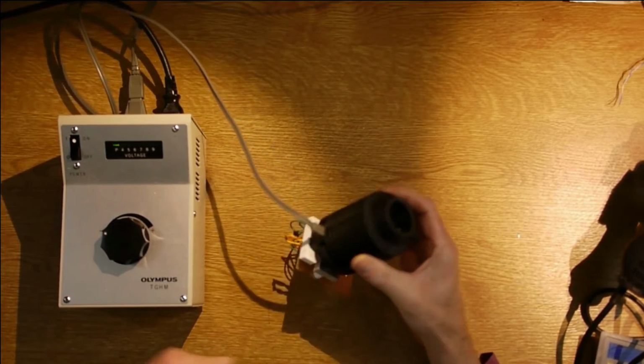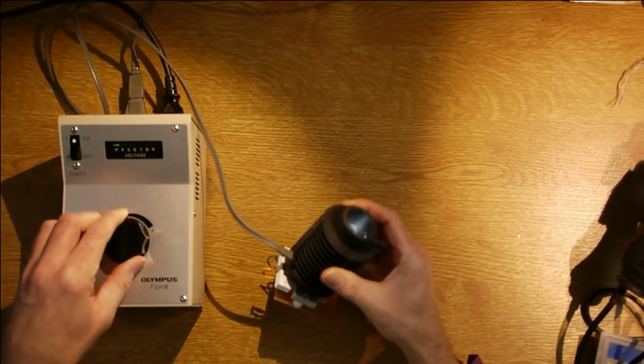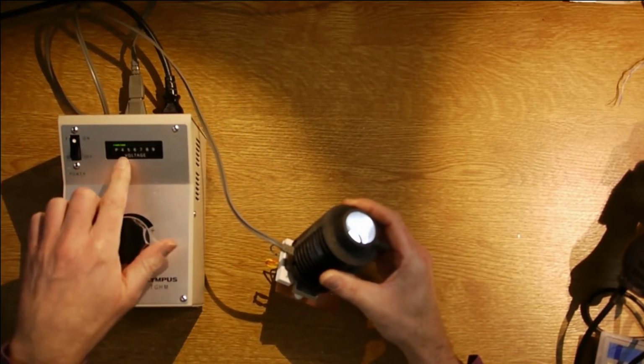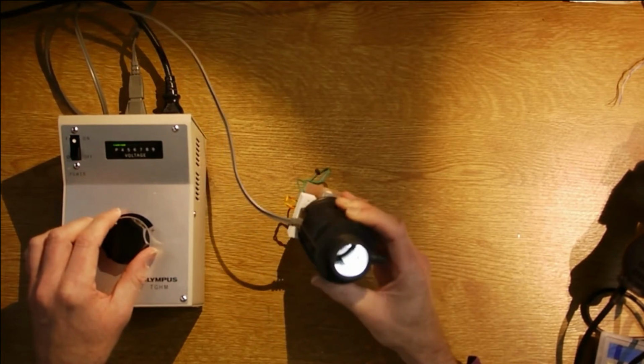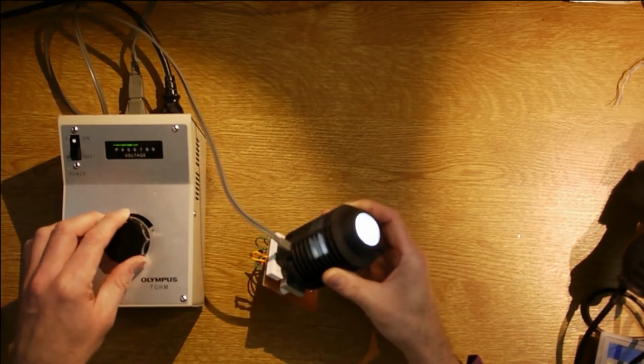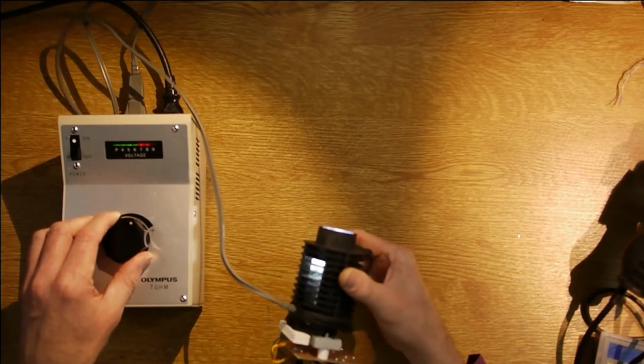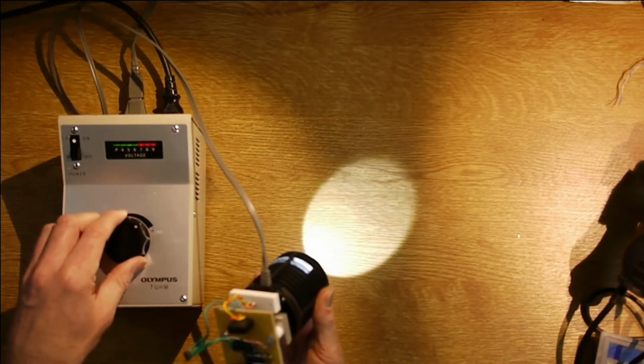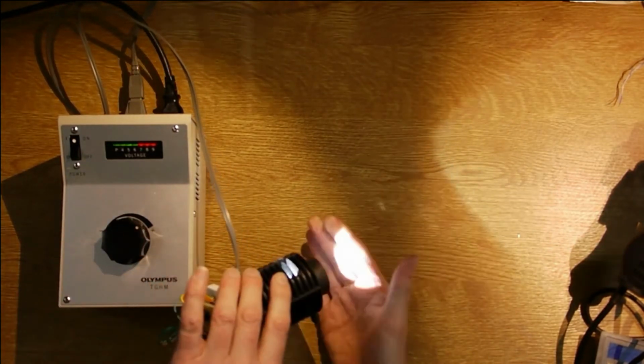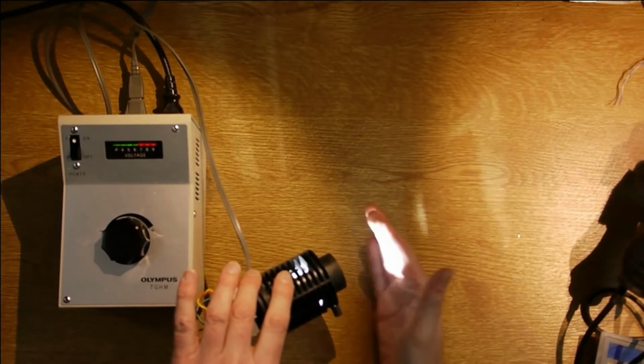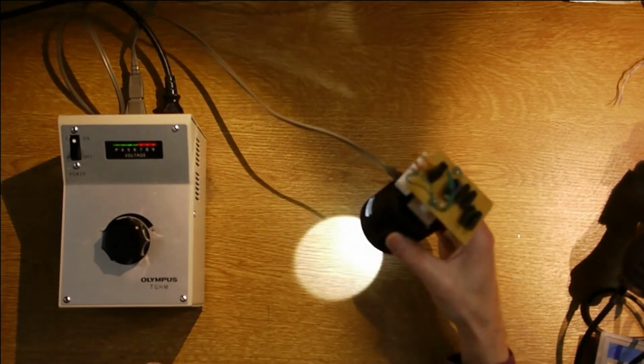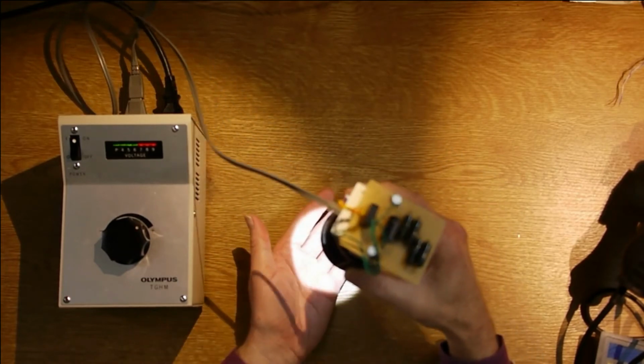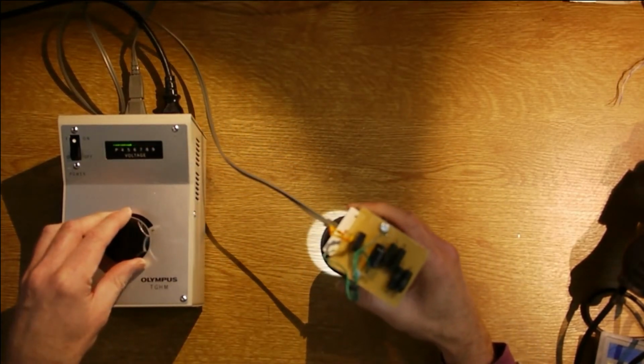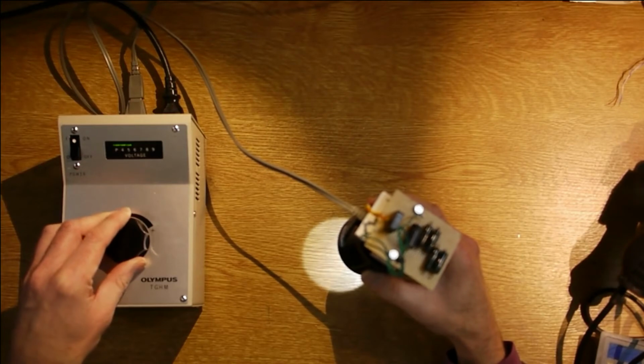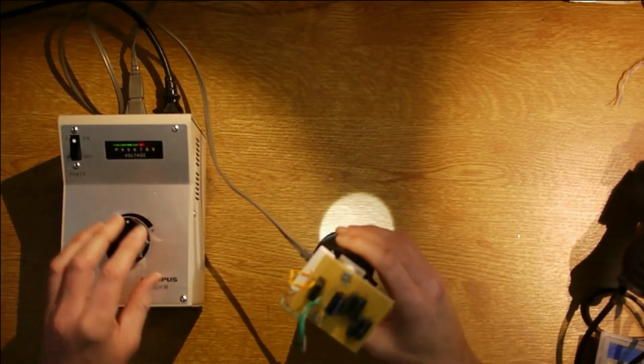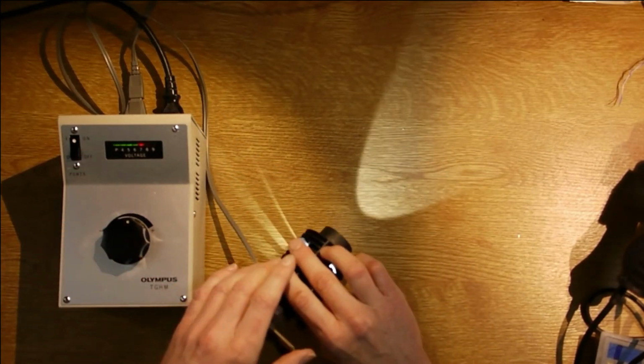That's the illumination. So if I turn it up, you can see that the LED is on at just 4 volts at the moment. And that's pretty bright. And you can keep going, get brighter and brighter. You end up with a pretty strong illumination system, and you can see that it's a nice even illumination as well. I use it sort of down here on 4, 5, 6 volts. Don't need to go to the higher voltage very much at all.